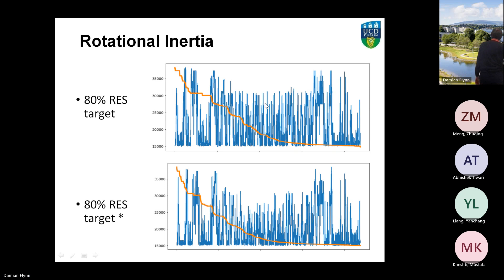Doing something similar for the combined cycle gas turbines, counting the number of units, you can see we might be as high as 14 units, which is even small for Great Britain, but we're going down to 4 units. Really those 4 units aren't there for energy, they're there for voltage support, synchronization, fault level, and other stability issues, and they're spread around the system. So it's really pushing the system to the edge.